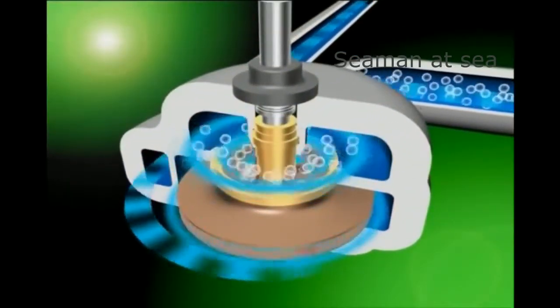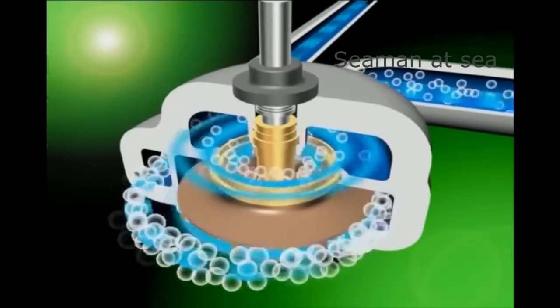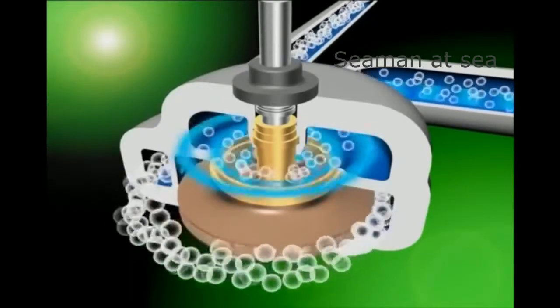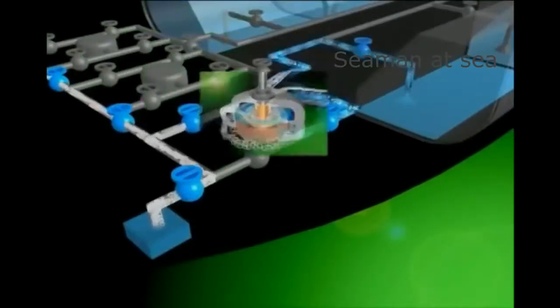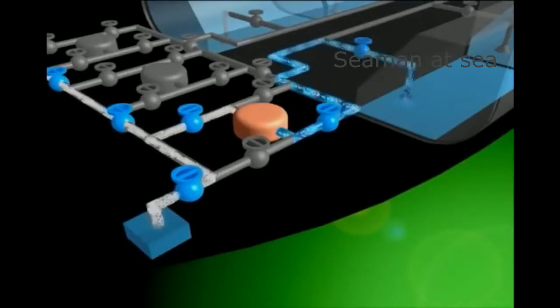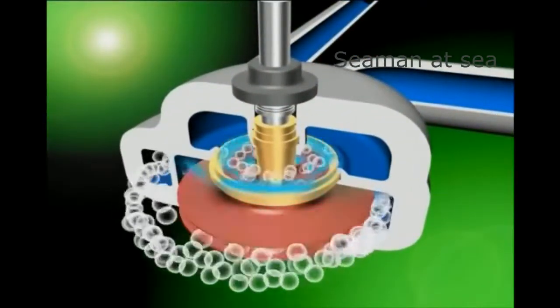When a small amount of air is drawn into the pump, the air passes out of the pump together with the seawater. But if a large amount of air has entered the pump, it gathers and gradually spreads to the pump periphery, decreasing the centrifugal force the seawater receives from the impeller and disabling the pump from discharging. If the discharge amount is extremely small, unnoticeably small amounts of air can gather within the pump and build up to a level that could disable it. If left as is, seawater in the pump will run out, resulting in burn.